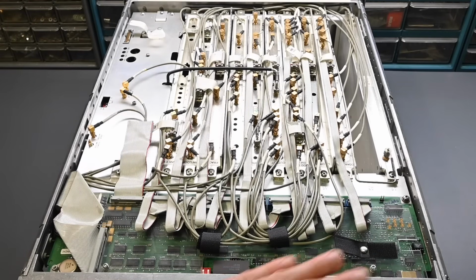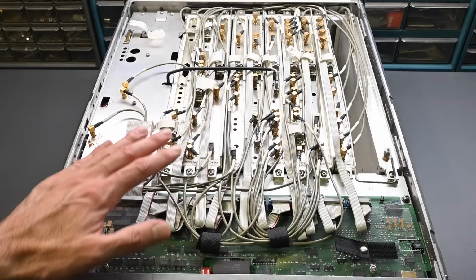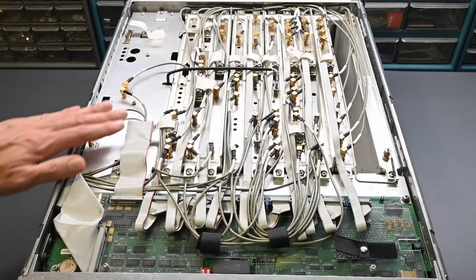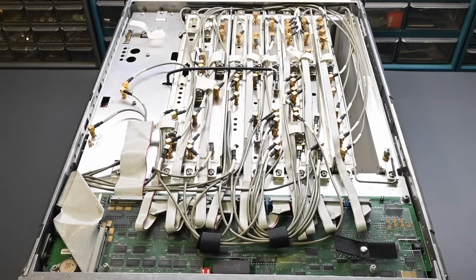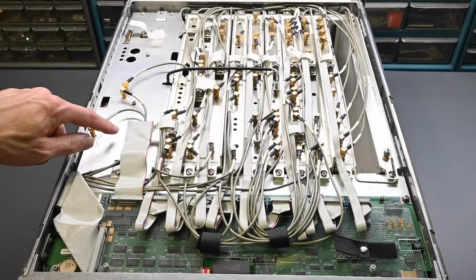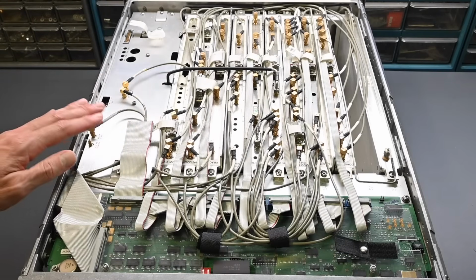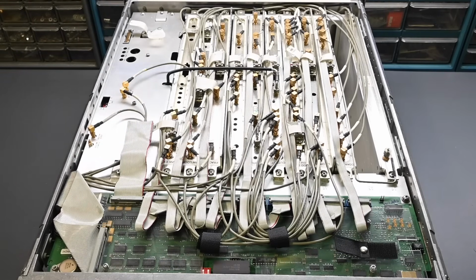So from what I can see, everything looks to be in good condition up in this top area. Now this section over here is where the battery will be located. It's on the main controller. So I need to remove this cover, some coax cables, and get access down in there. And by the way, there's two styles of covers that were used on these instruments. So this model has the two-piece cover, so the top and bottom are separate. There's also a single one-piece type of cover. So if you're working on one of these instruments, they might come apart differently depending on the type of cover that the instrument has.